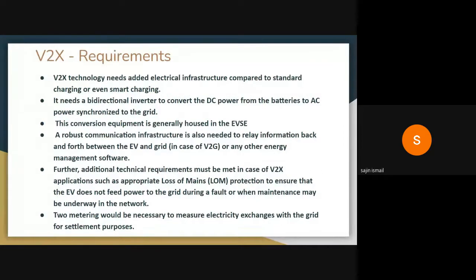That creation is going to be the biggest challenge when setting up EV charging infrastructure connected to the vehicle V2G system. Additional technical requirements must be met for V2X applications, such as appropriate loss of mains detection. This is like the anti-islanding effect in solar PV applications, where solar panels are connected to the grid. We need to make sure that when the grid has a power failure, or is operating under maintenance, the power generated from the solar panel should not go to the grid.